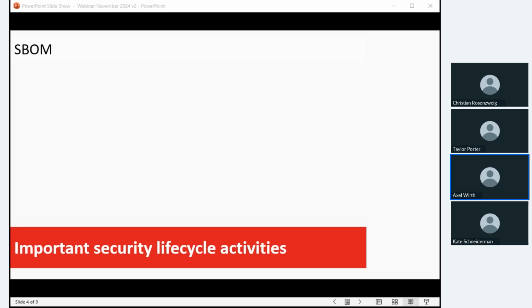And then lastly, getting back to my previous comment about, okay, granted, Windows 3.11 is a very simple example here. It probably wouldn't need an SBOM to identify that particular problem. There should be other more basic vulnerability, software documentation that the manufacturer should provide that gives you the insight on the level of the operating system. For example, the manufacturer disclosure statement for medical device security, short MDS2, that NEMA provides as a template, and that manufacturers can provide together with other security documentation. But again, that is only a solution, I think, for this very simple example. If you go deeper, log4shell, for example, you do need an SBOM. You do need the deeper analysis.